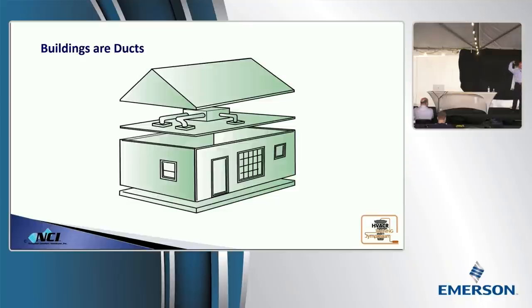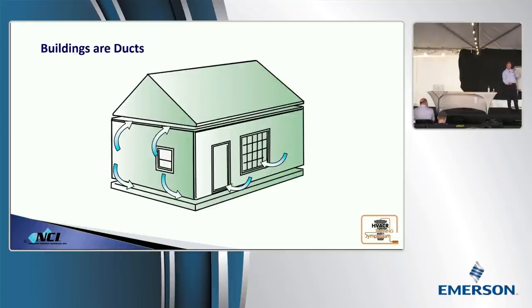Notice the duct system as it goes through and penetrates the ceiling. It becomes a part of that building at that point. Any penetration through that drywall becomes part of the building. So we have to account for how that pressure difference is going to change, because if it does, and it will, it's going to affect combustion air, how it's entering. Sometimes it'll work great. Other times, not so good. We take all these materials, we start to smash them together. We start to crunch them down, and we start to make them fit.